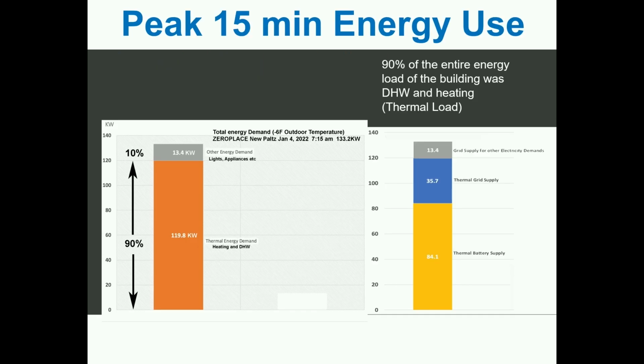One of the things I want to emphasize here, and I did this before, this is the total energy in the peak 15 minutes at 7 o'clock in the morning, and this is the most efficient building I know. And despite that, 90% of the energy was used for heating. That's the monster. But if you now look where the energy was coming from, about 70% of that huge load was coming actually from the loop field, from the thermal battery in the ground.